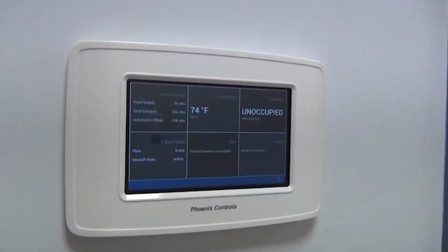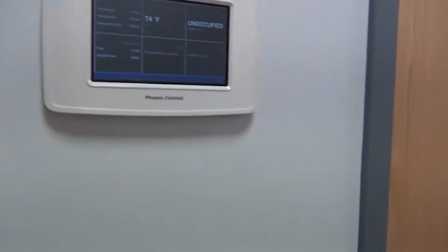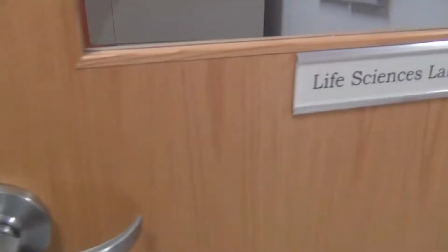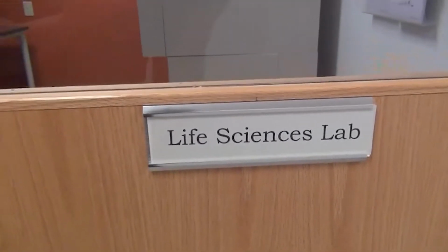Another room that we have as part of our Phoenix Controls research demonstration suite is this life sciences lab. Now, over the past few years, we've noticed that research has been changing dramatically. We used to be very fume hood intensive in these wet chemistry applications, or for pharmaceutical manufacturing and things like that. There were a lot of wet chemistry hoods in those types of applications, so they would have very high air change rates in those labs. You'd have great turn down on your fume hoods and on your general exhaust and supply, and you also need to be able to maintain that speed of response.